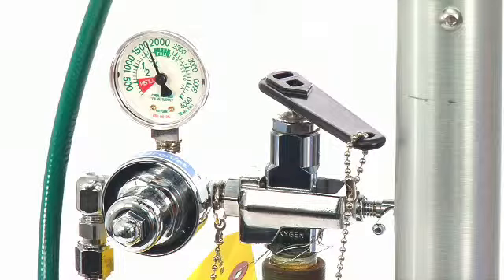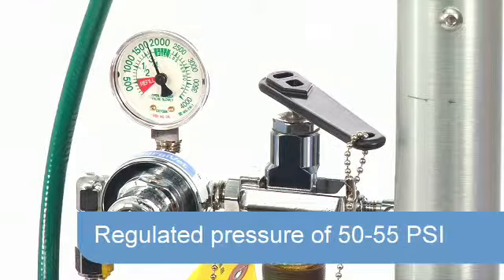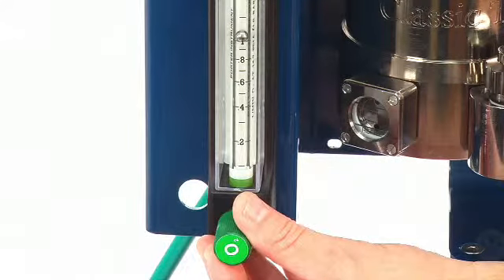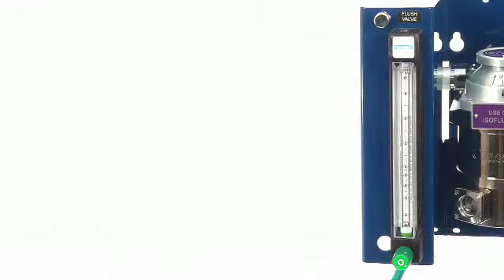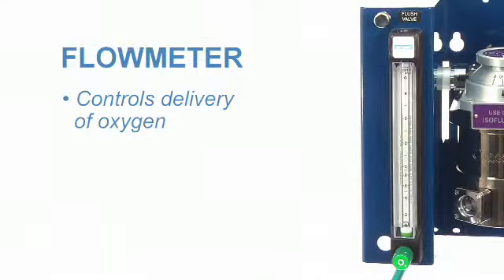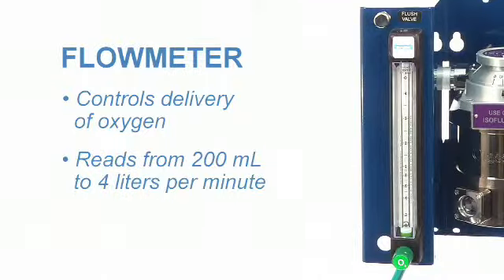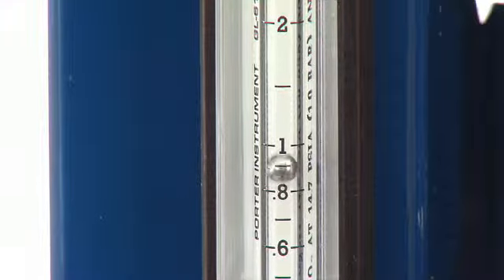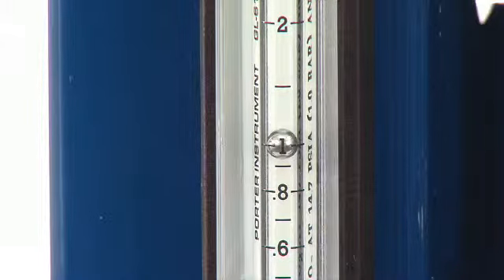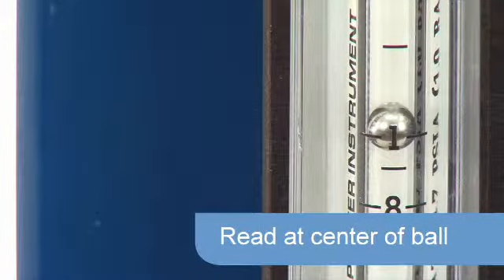Prior to use, confirm the gas delivery is properly connected and regulated with a line pressure of 50 to 55 psi. The flow meter is located on the far left side of the machine head. It controls the delivery of oxygen into the system. The standard flow meter reads from 200 milliliters to 4 liters per minute. The ball float, located inside the Thorpe tube of the flow meter, displays the amount of delivery gas being delivered to the system. It should be read at the center of the ball, not above or below.